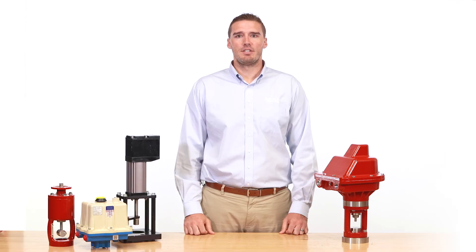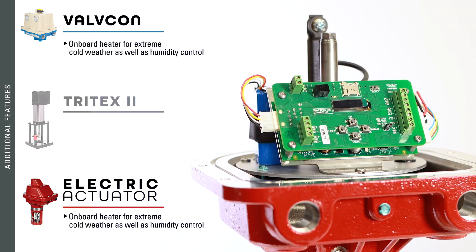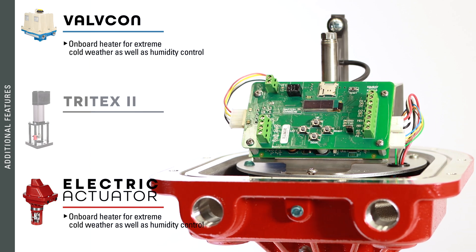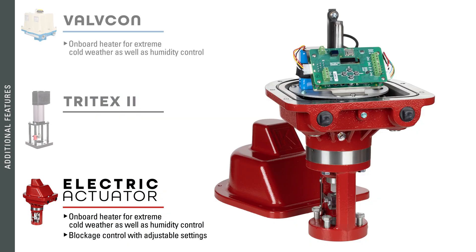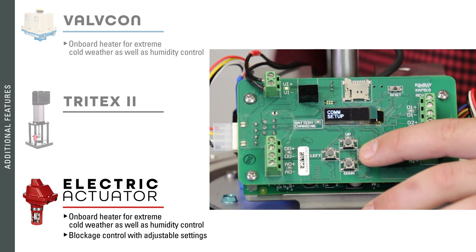A couple of additional features to consider are temperature control and blockage control. Both the Valvcon and Kimray electric actuator feature an onboard heater for use in the event of extreme cold weather, as well as humidity control. In the event of blockage in the bottom works, the Kimray electric actuator will increase the pressure and time between actuation to try and clear the blockage, and both of these settings can be adjusted via the user interface.